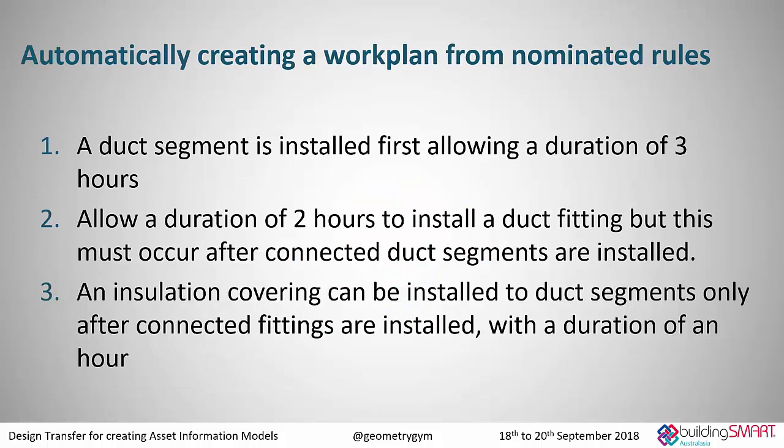And here we have just a network of ducting with some air terminals and some air handling units, etc. And what Peter gave me was three rules to try and produce a work plan so that we know what task needs to be done before other tasks can be started. And the first rule was that a duct segment is installed first and foremost, and we have to allow for a duration of three hours to install that air duct. If we have adjacent duct fittings, they can only be installed after the duct segments.